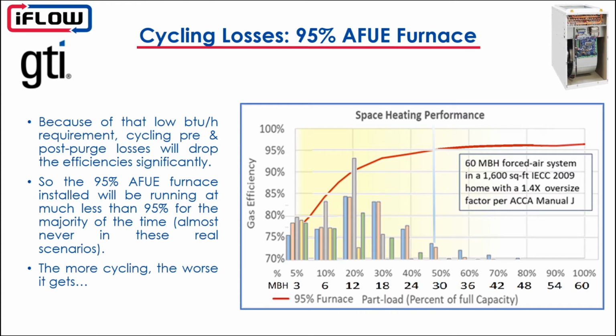And here we get into a look at how those units might perform. So in this diagram, we have a 95% AFUE furnace. It's a 60,000 BTU furnace. And you see here's the AFUE curve, the efficiency curve as it's modeled against the distribution of usage. You can see here that with this vertical line, it hits 95% AFUE, the stated AFUE, only at the 30,000 BTU range, or 50% of its capacity. From 30,000 BTUs to 60,000 BTUs, this furnace is going to operate at or above its 95% AFUE threshold, which is excellent.